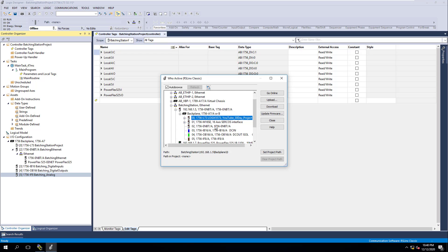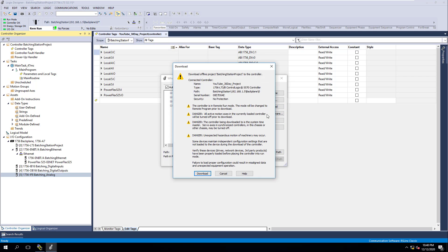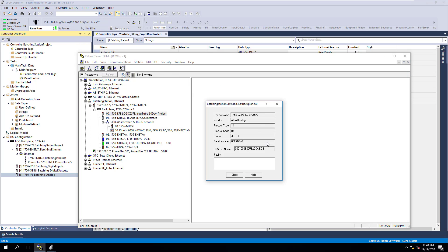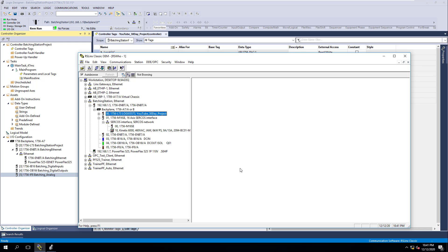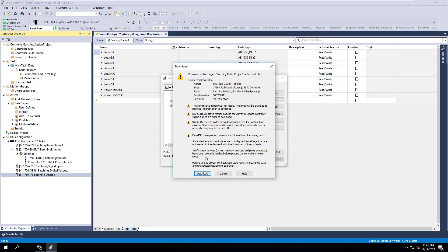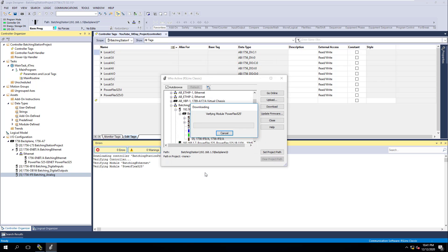We're going to click download. Now you do need to have your processor flashed to the version that you are currently going to. We already have our processor at version 32 already, so in this case we're completely fine. But if you did not have your processor in the correct version, you will need to change your software package to match your processor, or flash the firmware of the specific processor to match what you have. In our case, we match perfectly. We have version 32 software and version 32 flashed to our processor.